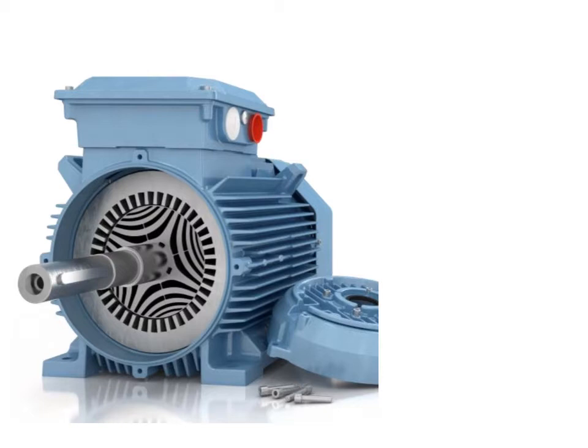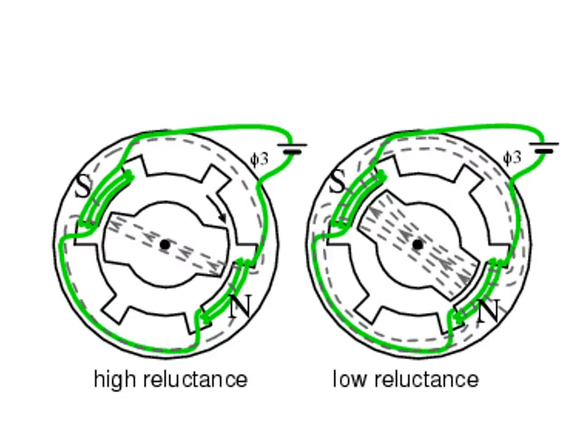This is a pictorial view of the reluctance motor — the yoke, power supply, stator, rotor, and shaft are all visible in the complete setup. The operation is straightforward: when we provide a three-phase supply, the armature produces a rotating magnetic flux. As the flux changes, the rotor moves from high reluctance to low reluctance paths continuously, causing the rotor to rotate continuously. We get mechanical output from the rotor itself — this is how it works, moving from high reluctance to low reluctance.